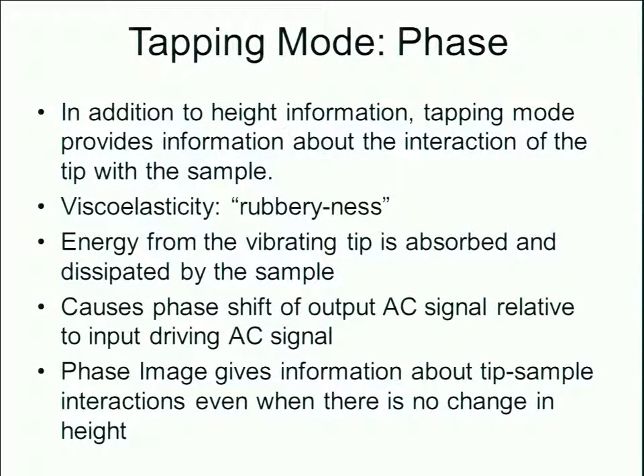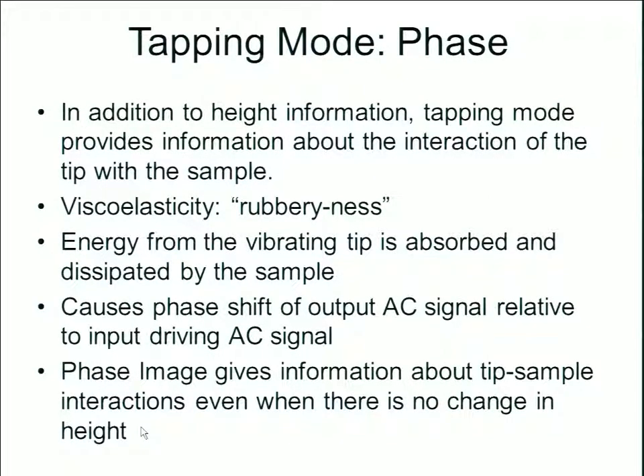In addition to height information, we can get information about the interaction of the tip with the sample, providing details of viscoelasticity and surface energy. The phase shift data will give us relative information and can tell us about the sample even when there is no change in height. If a sample is atomically smooth, we would still be able to detect differences between two different types of materials due to the phase shift lag or amplitude change from the tip-sample interaction.